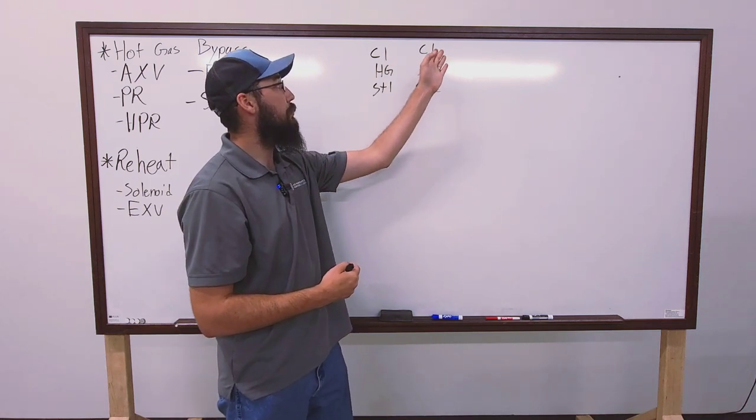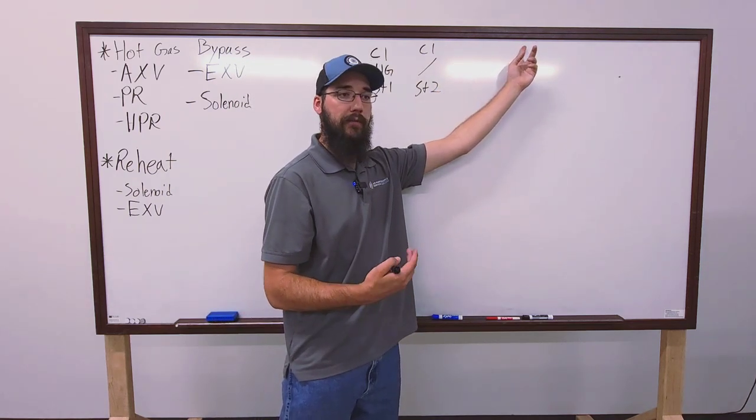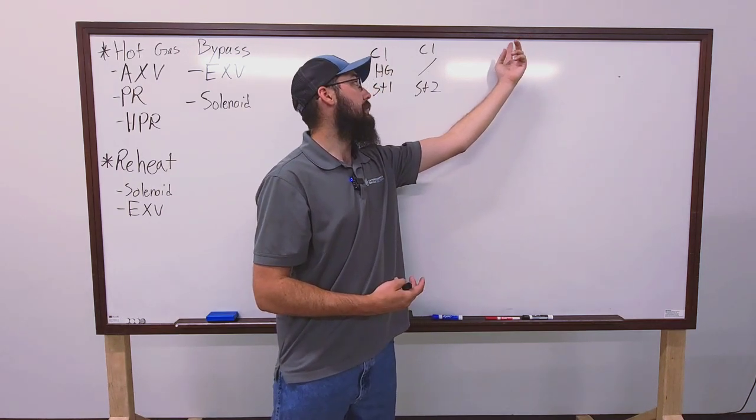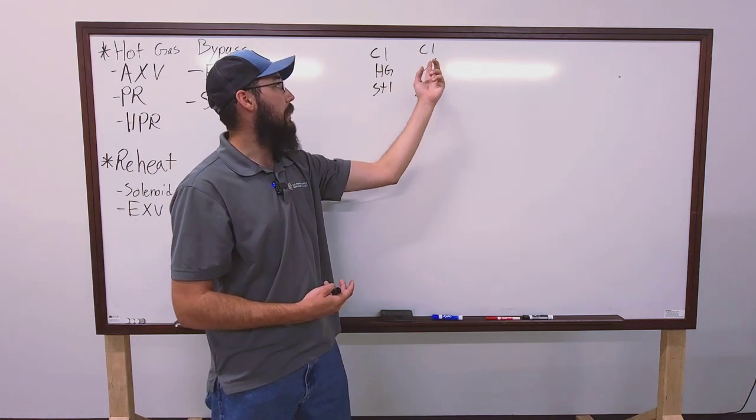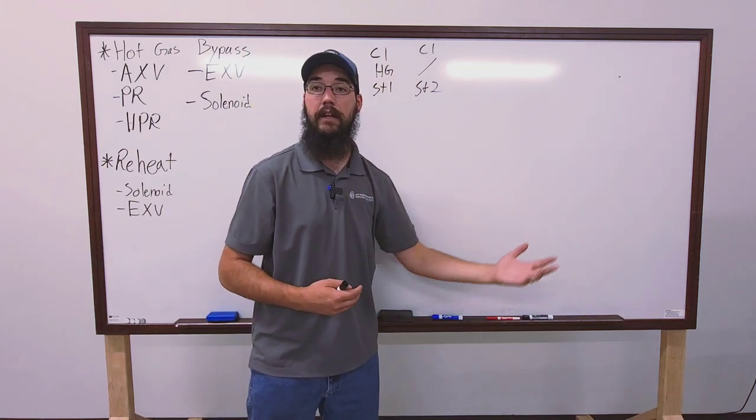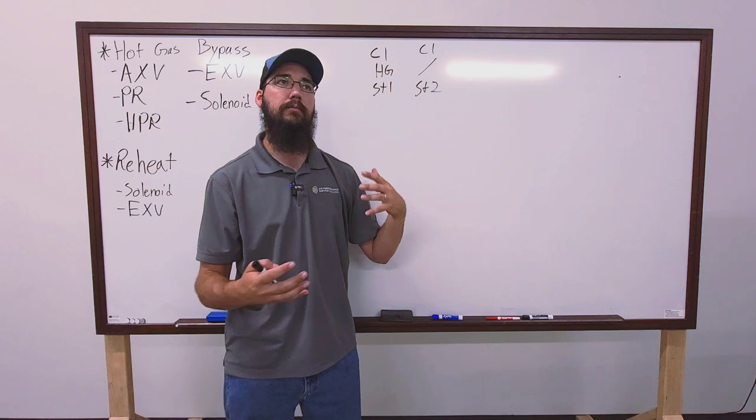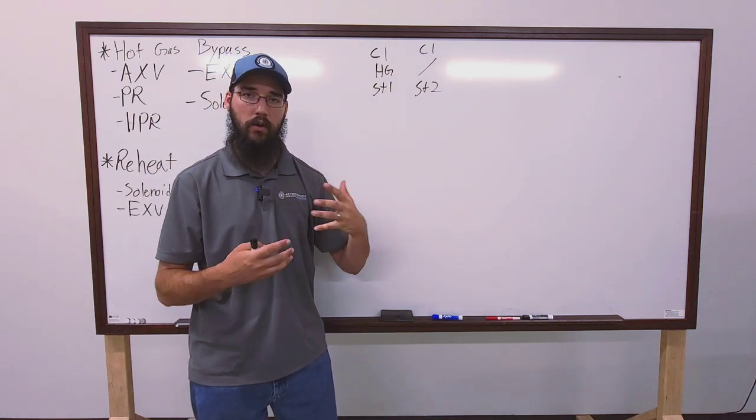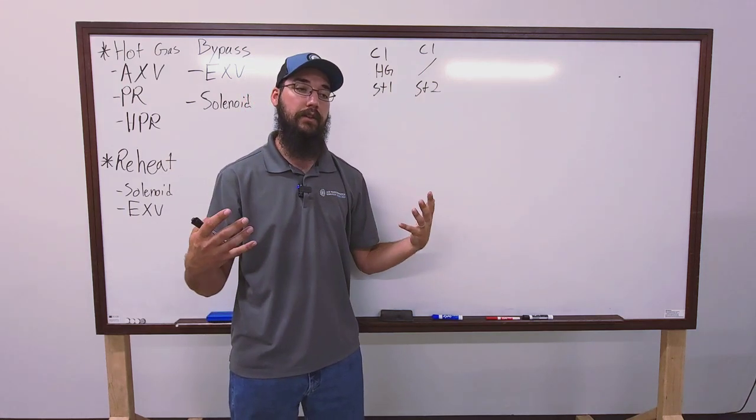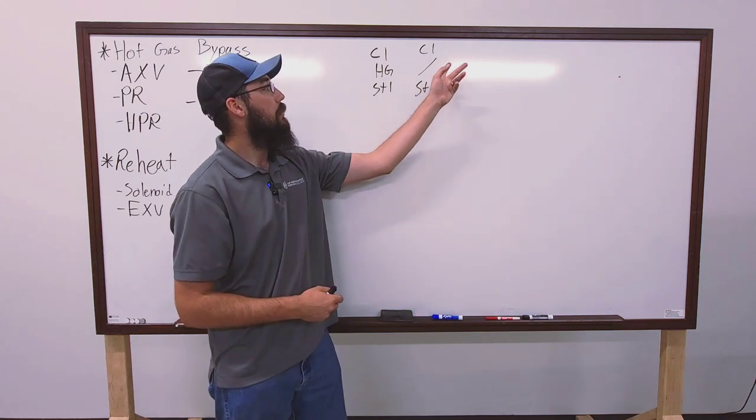So we're trying to produce a 55 degree discharge air on this system. That's our set point. As we're rolling through, we know that if we stage down far enough, so let's say we needed stage four in this particular case would be three compressors. So we are staging down and we get to stage two and it's just running one compressor and we're still satisfying. Now this may be something this time of year, late in the evening, say after things are cooling off quite a bit.